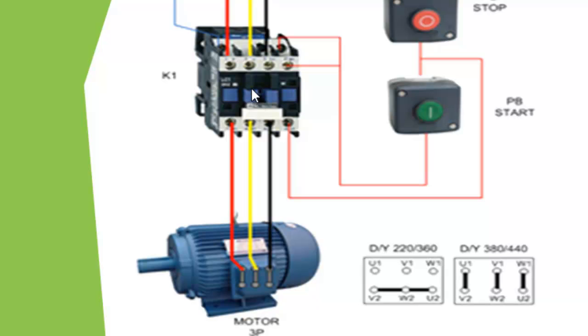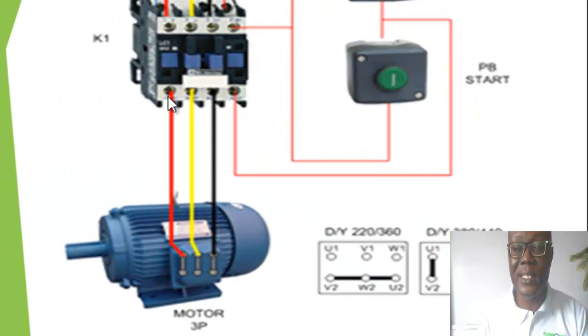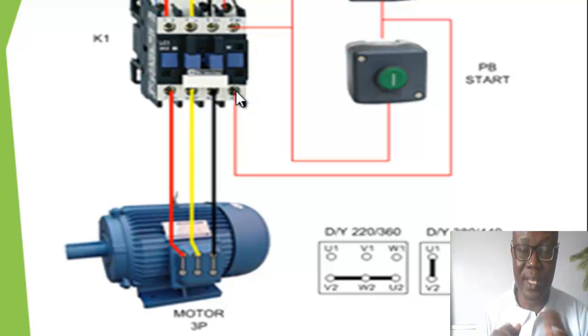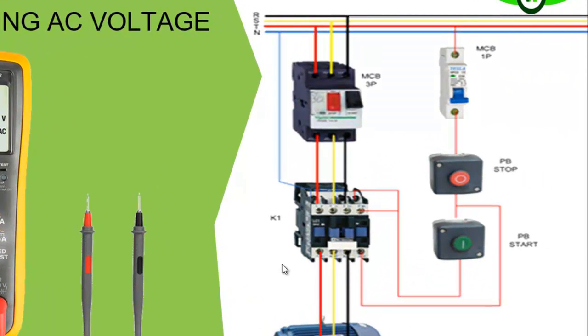Then you close the contactor now, and then test the line between the phases. When you get an output of 415 volts between line 1, line 2, line 3, line 1, line 3, you can confirm that the contactor is okay. Okay, so if it is not giving you an output, then it means something is wrong with that contactor. So you carry out further troubleshooting to ascertain whether the contactor is working or not, or the problem that is with the contactor. Okay, so that is for the power circuit. Now, if you look to the right, you will see that we also have a control circuit. The malfunctioning of the control circuit that is powered by AC can also disrupt the operations of your electric motor.